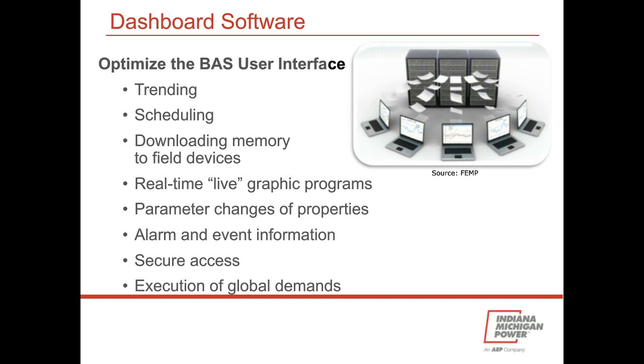You can choose an optimized user interface with whatever information you want, and change it at any time. So if you're having trouble with your chiller plant, you can bring in multi-trend graphs, the main system graphic, and maybe a specific I/O panel into your dashboard to get a picture of how that system's doing at the moment. Or maybe you want to see comparative energy or utility usage - you can bring in a variety of different graphs and charts and see immediately how that building's performing.